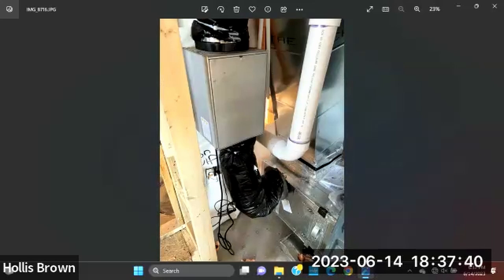Does everybody know what the gray box in the upper left is? Fresh air intake. It is a powered fresh air intake. There's actually a separate filter and a separate fan in that box. Most of the time when I open that box and take the filter out, it's got all sorts of crunchies on it because it's been running for months and nobody's noticed it. The duct that comes off of it typically goes right into the return. The input goes outside, and everybody likes to bend and twist it because it doesn't seem that important. That's what provides fresh air in all modern houses.